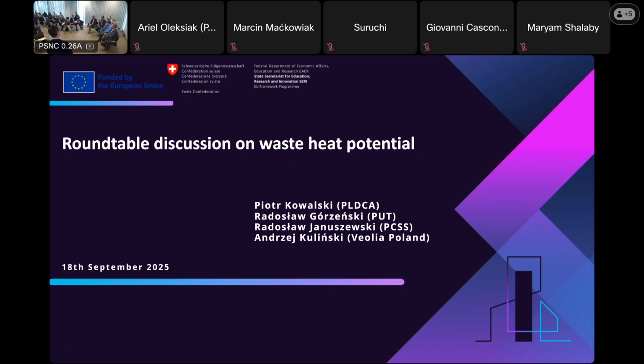If we compare the average temperatures of each of these sources with air, it's more or less 0 to maybe 5 Celsius degrees. The problem is that it changes a lot during a year. The second option is ground source, maybe 5 to 10 Celsius degrees, more stable but much more expensive. Then we talk about 30, 40 Celsius degrees.